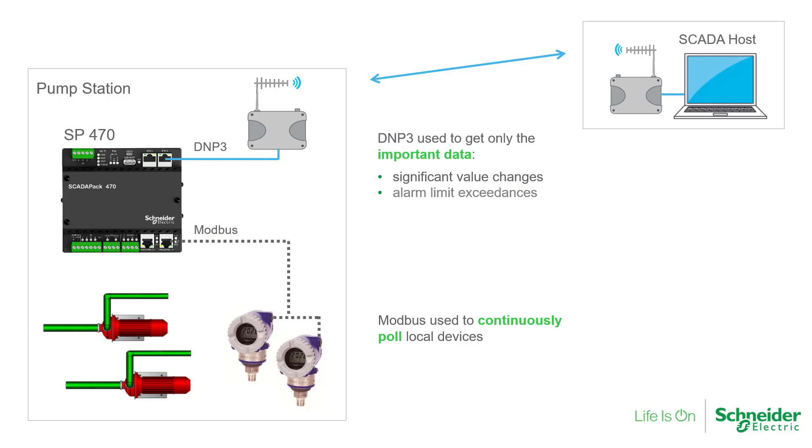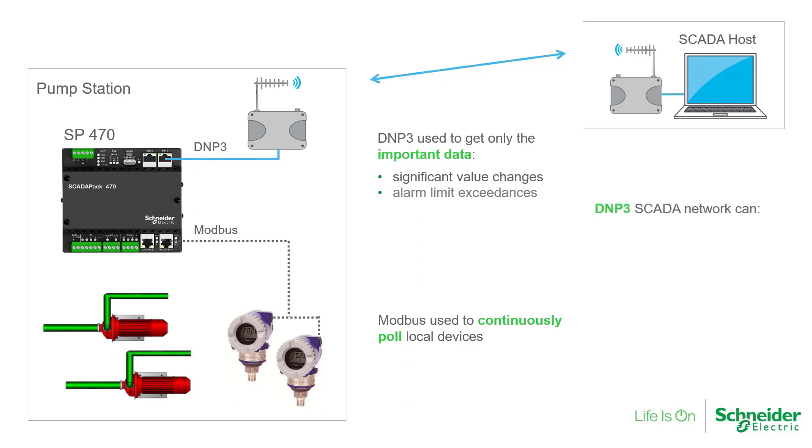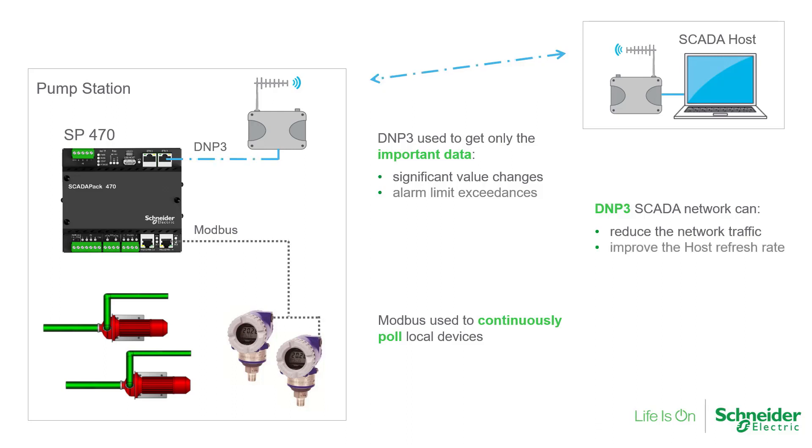Note that because only the important data is reported to the SCADA host, the amount of data communicated is much less than the data polled continuously between the RTU and the local Modbus devices. This is an advantage on the SCADA network, as the host will typically communicate with multiple RTUs and must allocate time for each. Reducing the amount of traffic on the network can improve the refresh rate of the SCADA host and can reduce costs when using a cellular network.